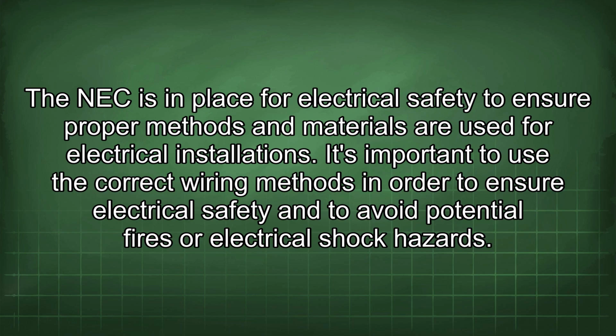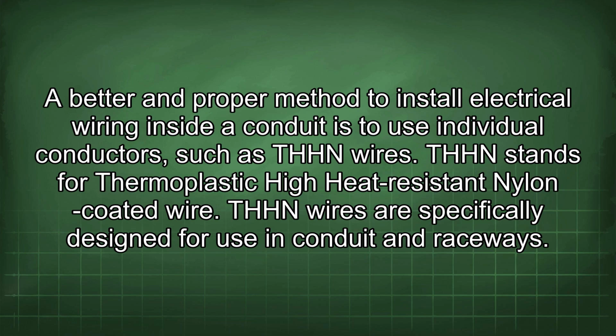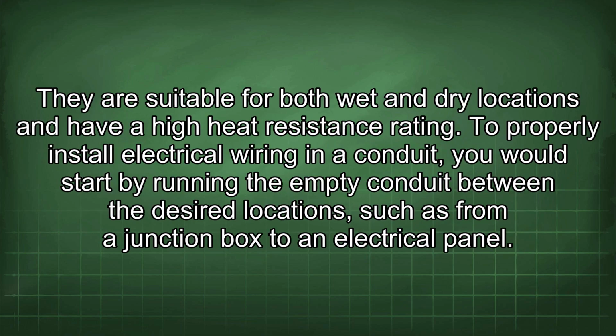electrical shock hazards. A better and proper method to install electrical wiring inside a conduit is to use individual conductors such as THHN wires. THHN stands for thermoplastic high heat resistant nylon coated wire. THHN wires are specifically designed for use in conduit and raceways. They are suitable for both wet and dry locations and have a high heat resistance rating.